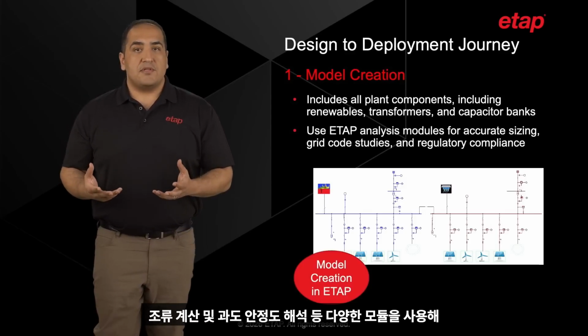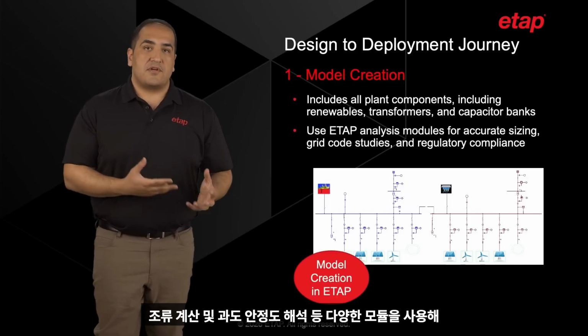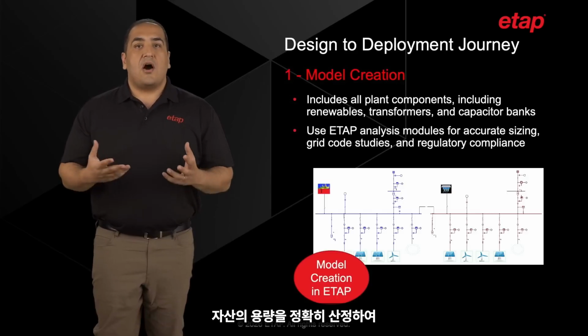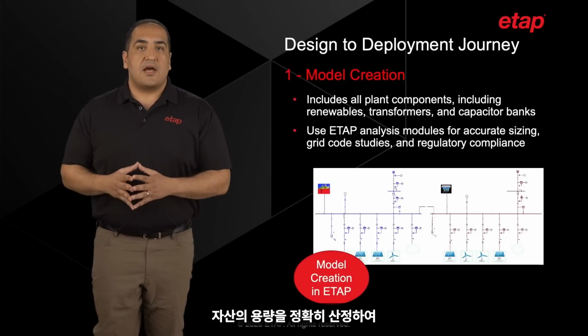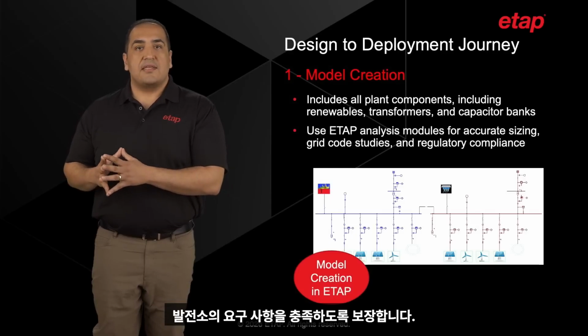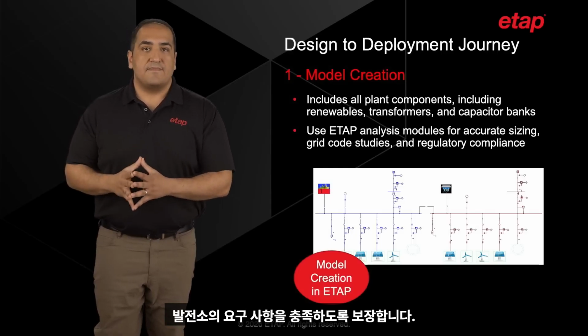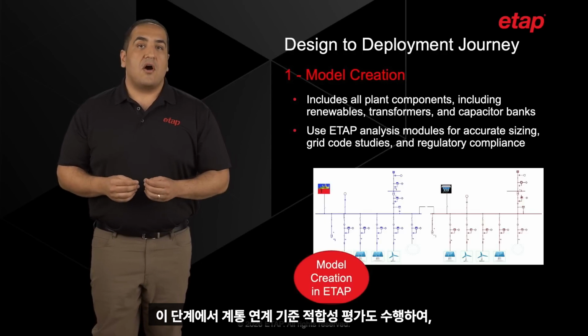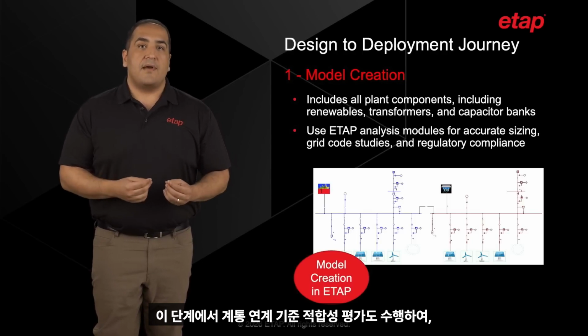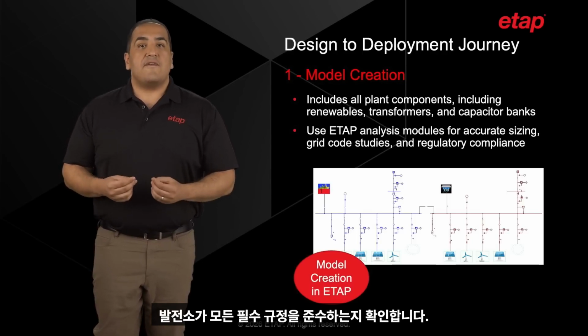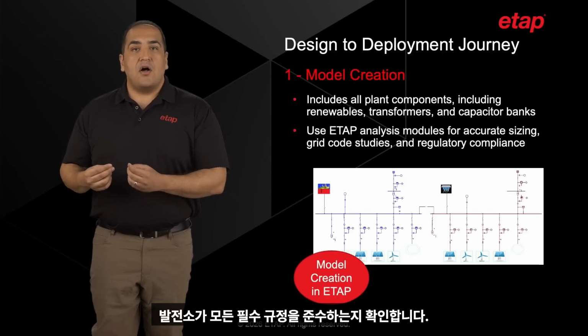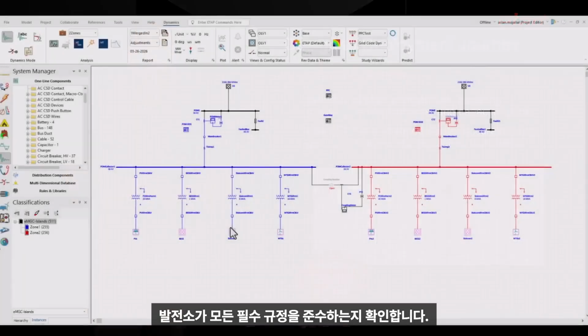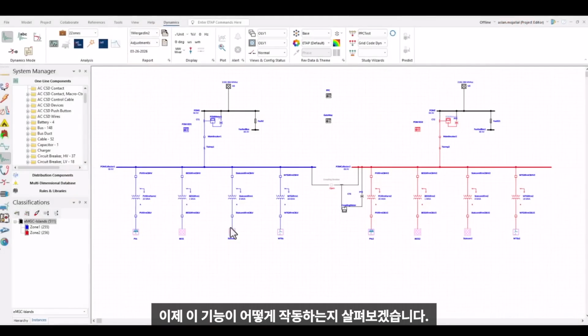Various ETAP modules, such as load flow and transient stability studies, are employed to accurately size the assets, ensuring that they meet the demands of the plant. Grid code studies are also conducted within ETAP at this stage to verify that the plant complies with all necessary regulations. Now, let's walk through how this works.